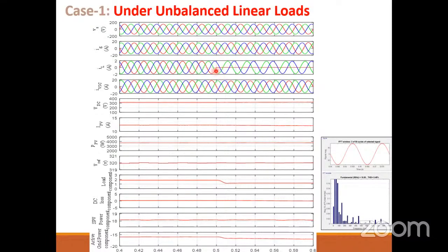And here unbalanced means at a certain moment one phase of the load is gone. So this is the load unbalance point when the load is gone. In this situation, what is going to happen? If one phase load disconnects, the load current consumption will decrease. So you can see here the load current consumption decreases, right? If load current consumption decreases, then the amount of power going into the grid should increase, right? So you can see here it is increasing.